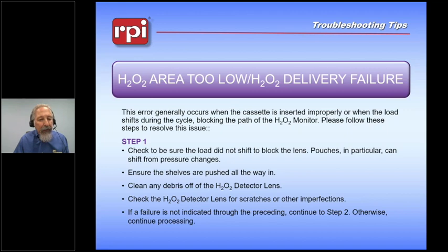There is also a possibility that there might be debris that has gotten onto the lenses. The two inner lenses are replaced as part of the planned maintenance, and we want to be sure that no material collects on them, has fallen on them, dust or whatever material might be within the inner chamber of this sterilizer.